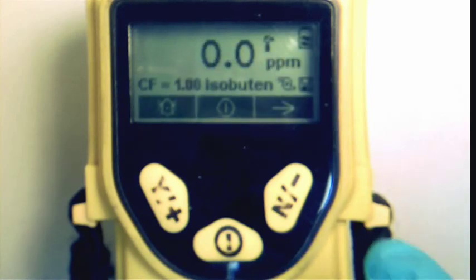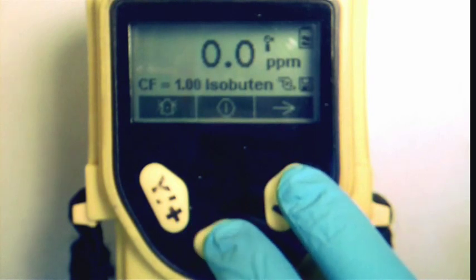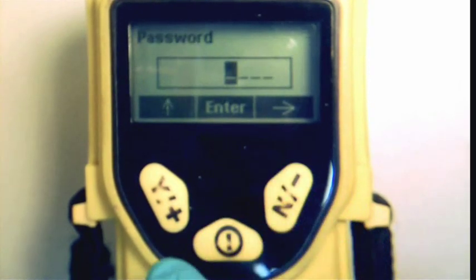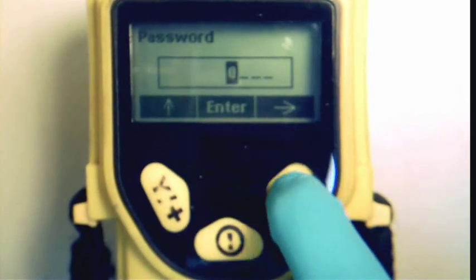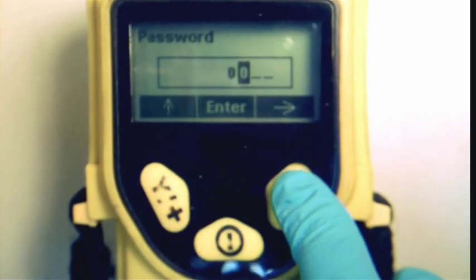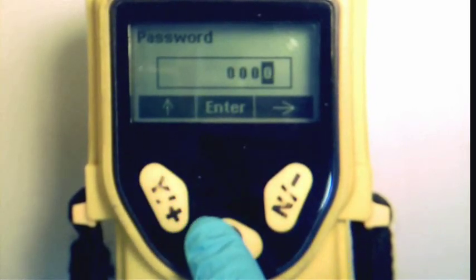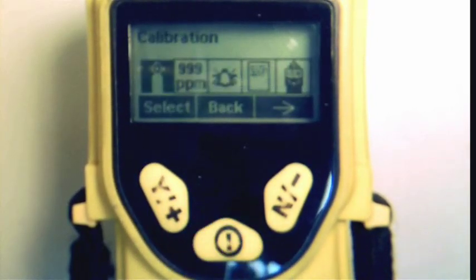Press and hold the power and end buttons together until the screen changes. Use the Y and N buttons to input the default password, which is 0000, and then press the middle button to move on. The unit will now display the setup menus. Please note the three icons at the bottom of the display — these icons will show the function of each button while using the MiniRAE 3000.